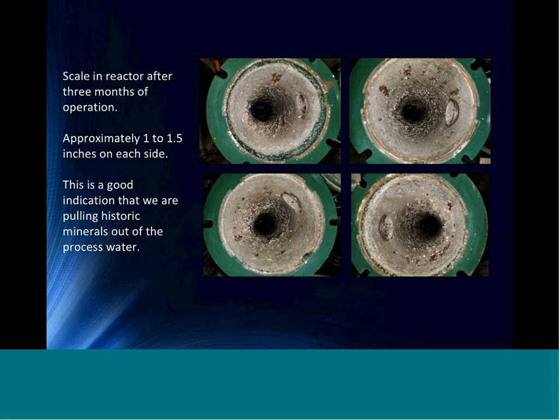Inside the reactor, we're pulling unstable mineralization. We're leaving the majority of the calcium, magnesium, and silica because we agree that is a great passivator, but also preventer of corrosion, provided it's in a stable state. By leaving the majority of those elements, we accelerate the scale formation that nature wants to deliver inside our reactors by creating a pH gradient from 0 to 14. We have a titanium anode in the center of our reactors, which allows for a low pH of around 0 with a high pH on the cathode wall of around 14. This directs the mineralization that wants to scale to form scale very quickly, about 1,000 to 1,500 times faster than nature would normally form it.